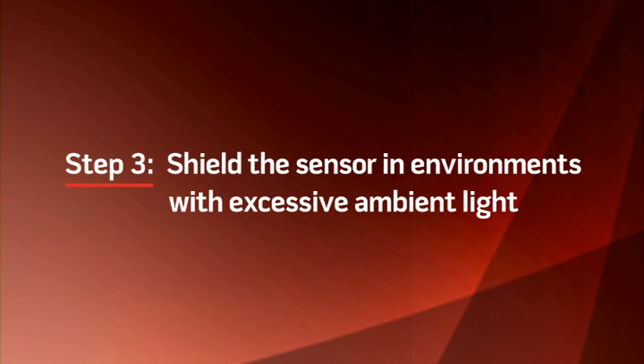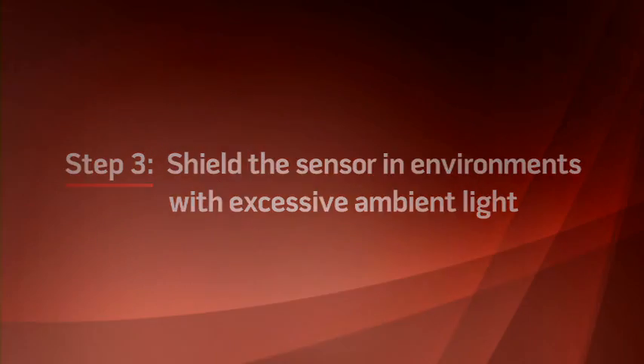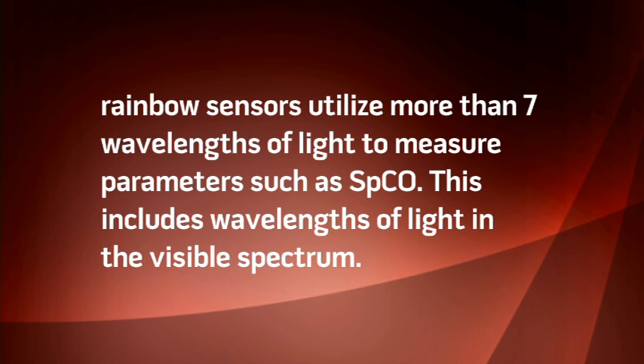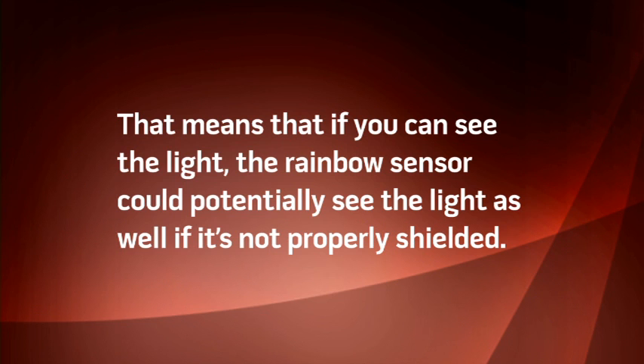Step 3. Shield the sensor in environments with excessive ambient light. Rainbow sensors utilize more than 7 wavelengths of light to measure parameters such as SPCO. This includes wavelengths of light in the visible spectrum. That means that if you can see the light, the rainbow sensor could potentially see the light as well if it's not properly shielded. Low-intensity light, such as light in the back of an ambulance, light inside of a patient's home, or the average light inside of a building typically will not interfere with the device.